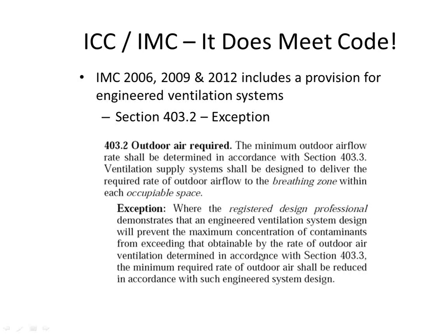And the International Mechanical Code does allow it down here with the exception where the registered design professional demonstrates that an engineered ventilation system design will prevent the maximum concentration of contaminants from exceeding the attainable rate by the outdoor ventilation method. So it is allowable with the International Mechanical Code.